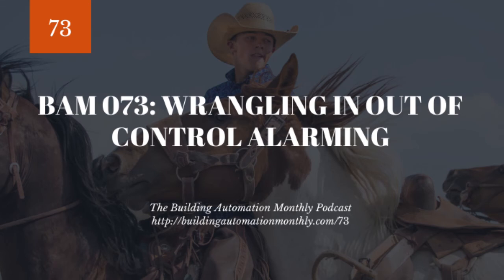What I mean by starting at the segmentation is that you're going to think about what systems are critical. You're going to look at the building automation system you have, and its capability for prioritizing and segmenting alarms. You'll spend an hour figuring out what categories you want. Usually it breaks down to 2 or 3 categories. You'll either have high, medium, and low, which I really don't recommend, or something like critical, priority, normal, which is more what I recommend. Then you'll go and put your systems in.